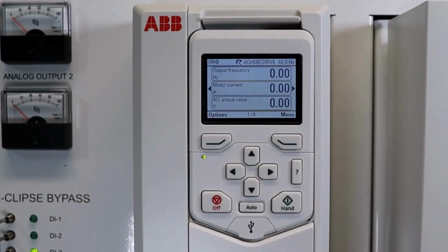What we can do now is we can tell the customer that there is a wiring problem. The information is not coming to the drive. And let's say the customer figures it out and then fixes it. There was a wire down at the freezestat or something like that that wasn't connected.